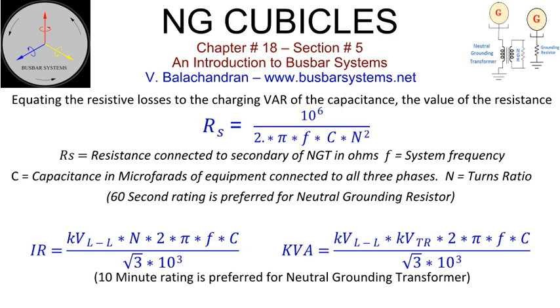It can be established that transient overvoltage can be kept low by sizing the resistor to such a value that its losses on a line to ground fault are equal to the envisaged capacitive reactive volt amperes of the generator connections of all three phases. The capacitance to ground per phase will be the summation of the capacitance of the generator winding per phase, the capacitance of the surge capacitor installed in the surge protection voltage transformer cubicle. If a generator breaker has a capacitor on either side of its pole, then both these have to be considered. The cable capacitance, if any, from generator connections to the startup transformer. The capacitance of the isolated phase bus and surge arresters are insignificant and can be neglected.